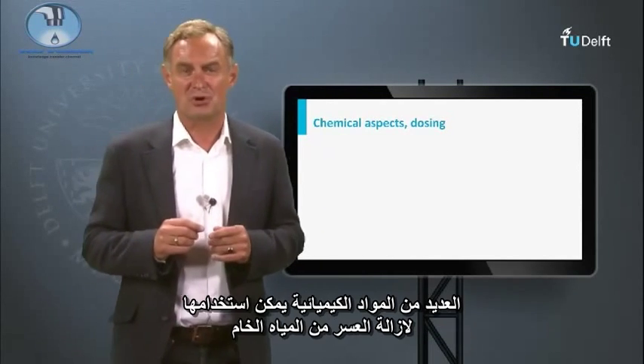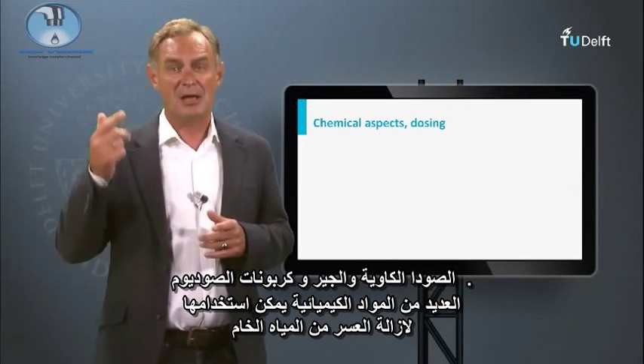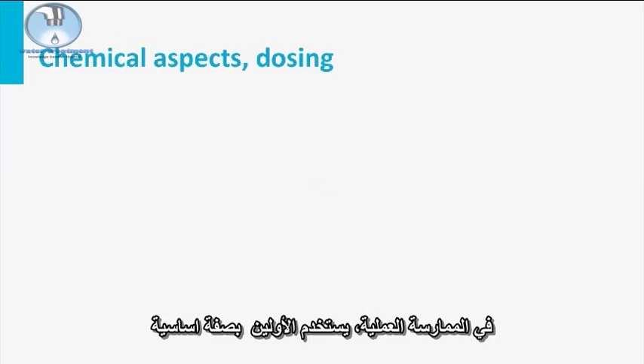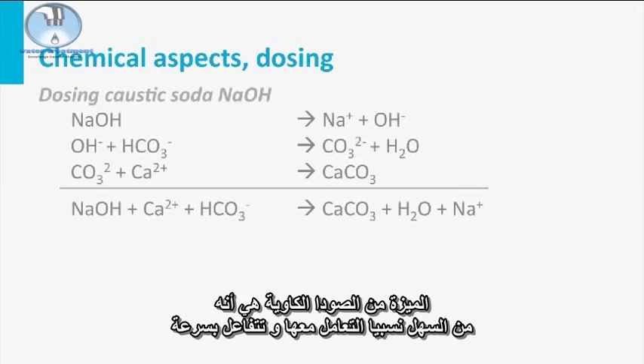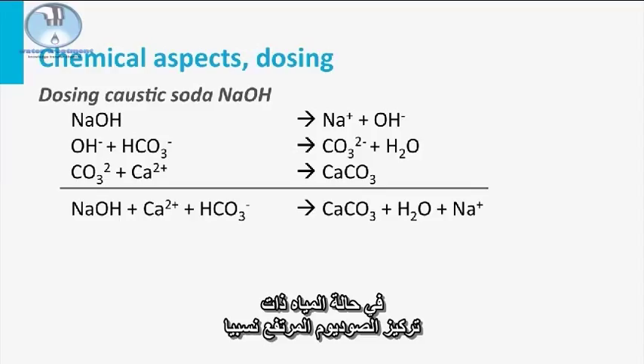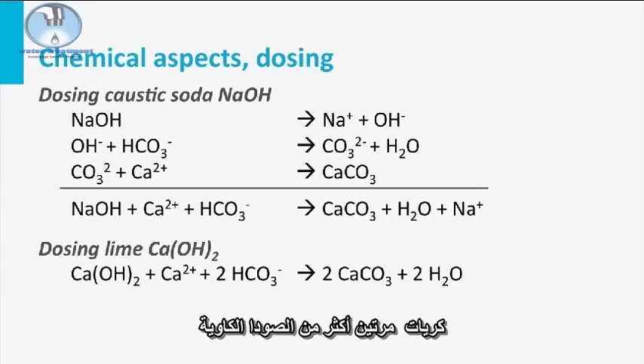Several chemicals can be used for the softening of raw water: caustic soda, lime, and soda ash. In practice, mainly the first two are used. The advantage of caustic soda is that it is relatively easy to handle and reacts rapidly. The disadvantage, however, is that sodium is added to the water, which can be problematic in case of waters with a relatively high sodium concentration. Lime is more difficult to handle, reacts slower, leading to higher reactors, and produces two times more pellets than caustic soda.